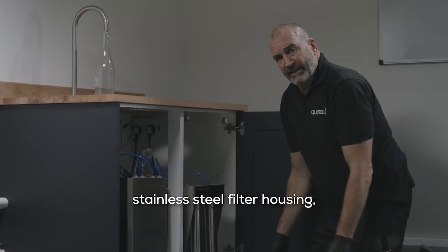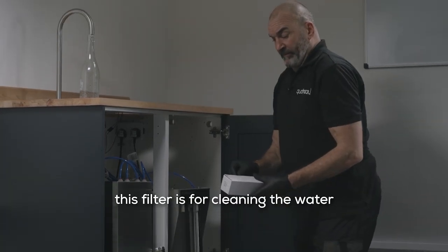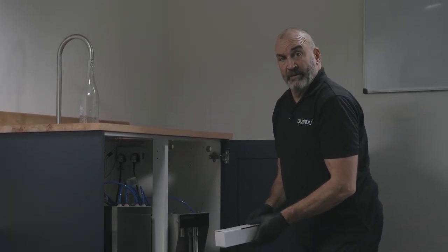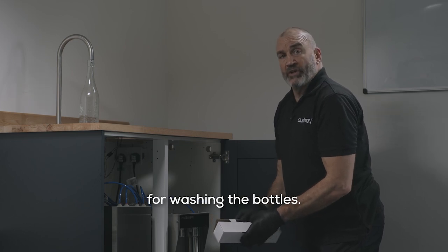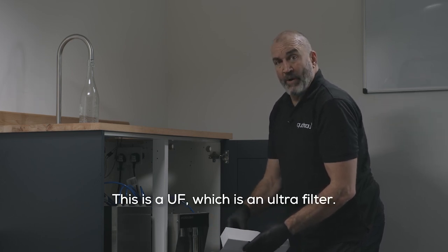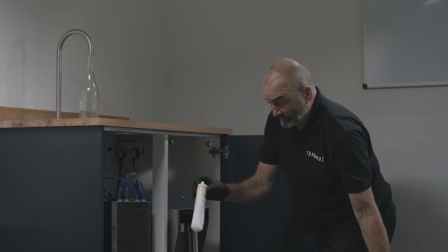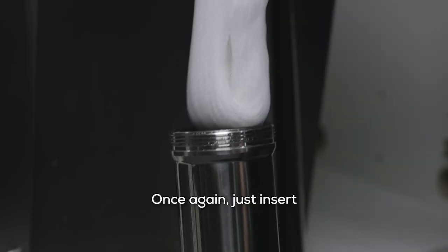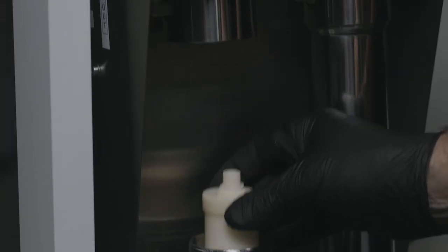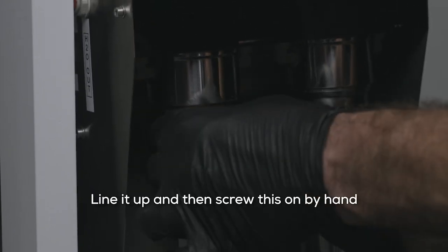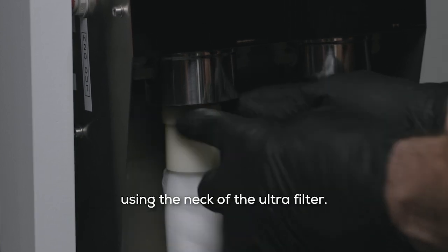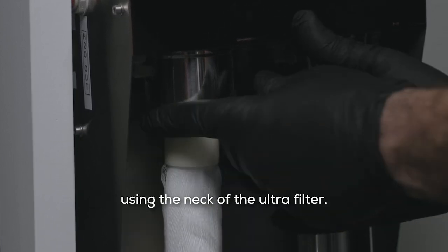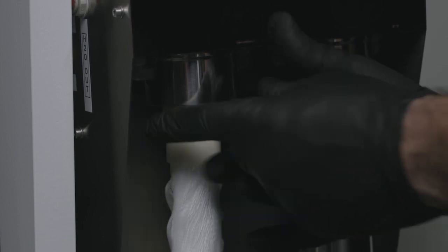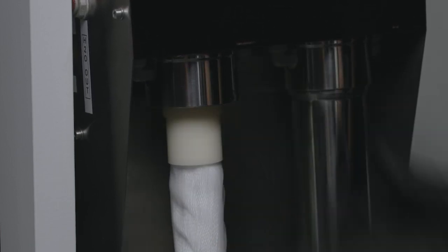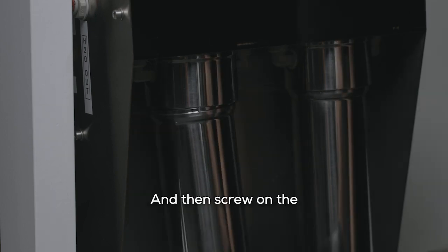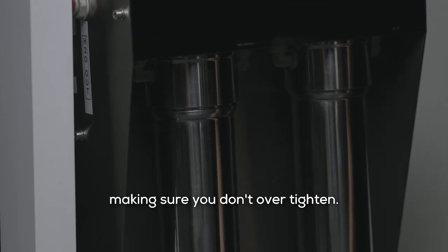And on the left hand stainless steel filter housing, this filter is for cleaning the water in the tank that is used for washing the bottles. This is a UF, which is an ultra filter. Once again, just insert this into this filter housing, line it up, and then screw this on by hand using the neck of the ultra filter. Screw it up until it's hand tight, and then screw on the stainless steel filter housing, making sure you don't over tighten.